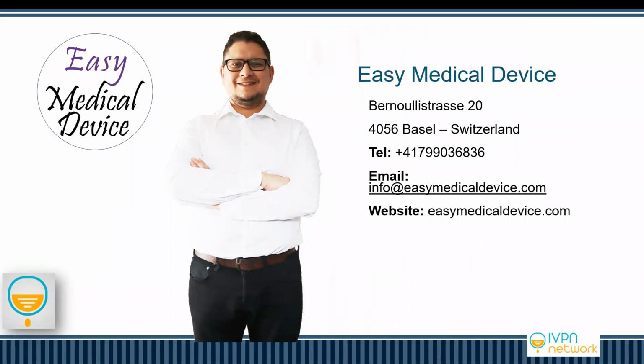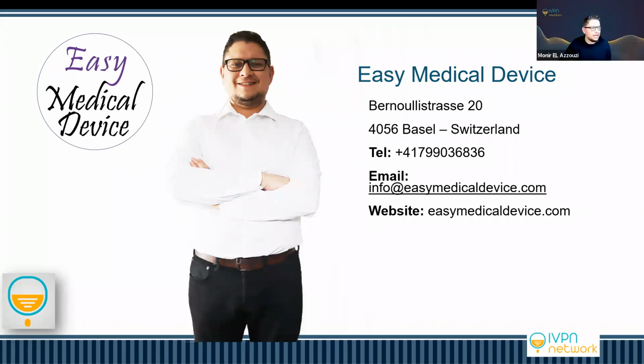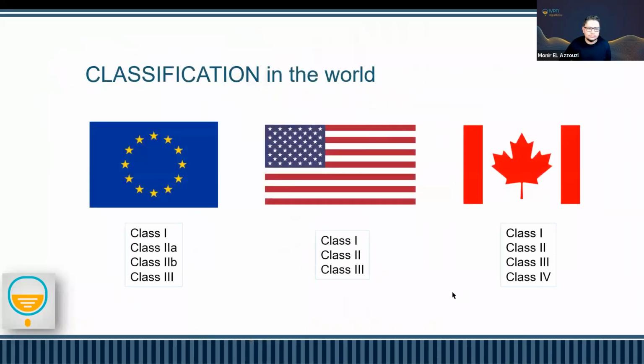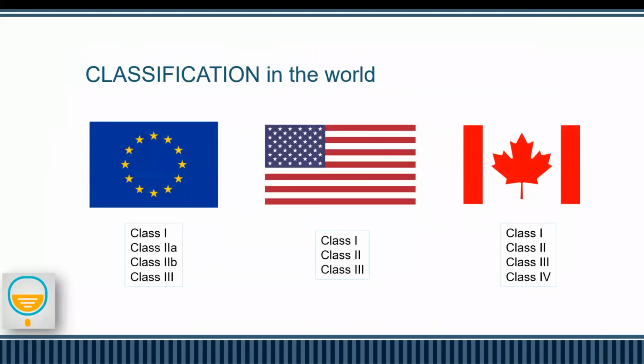I want to ask about the different rules between the US, Europe and Canada. In general, if, for example, the US wants to import some devices from Europe, will they follow the European rules or the US rules? US rules. It's the country where the product is received. For example, if the product was approved in Europe, you cannot import it to the US until the product has also followed the US rules.